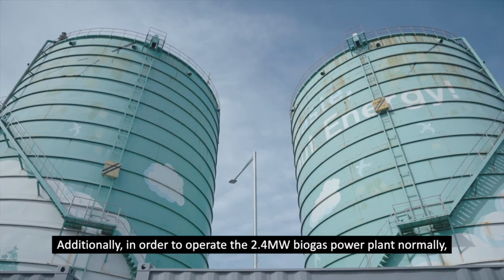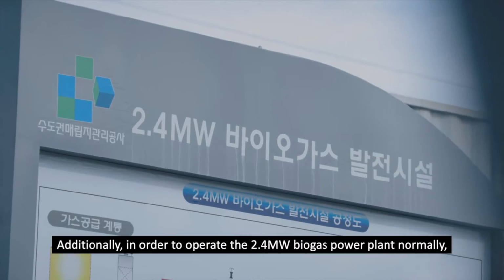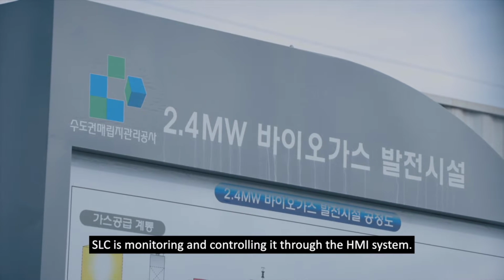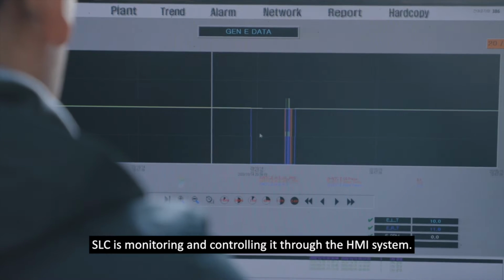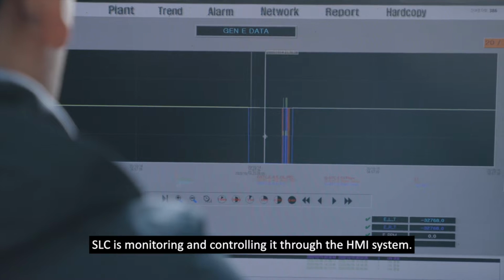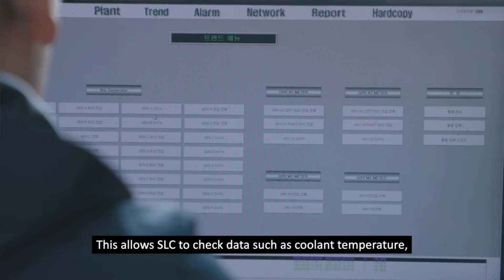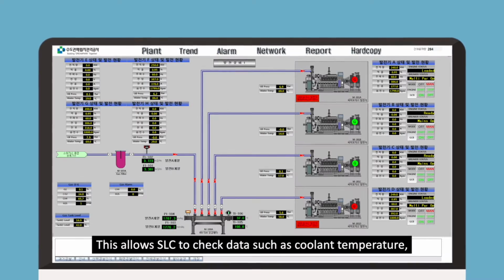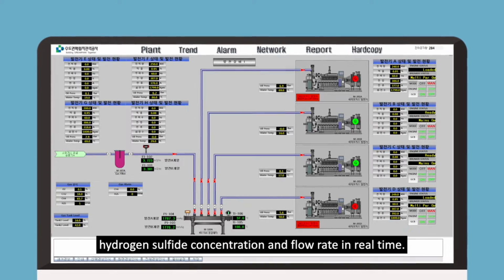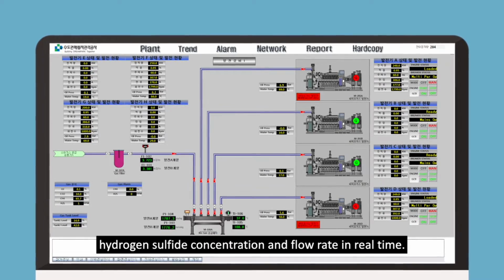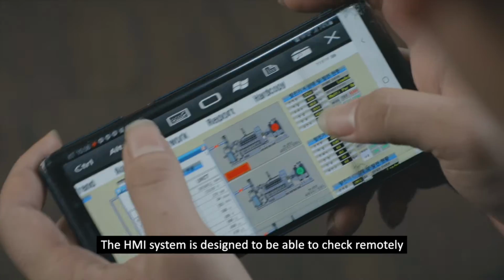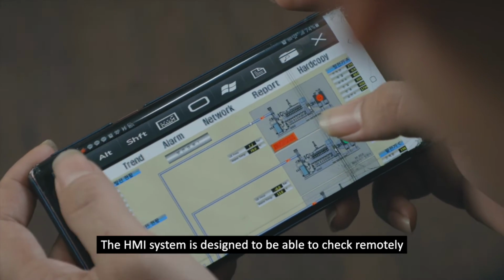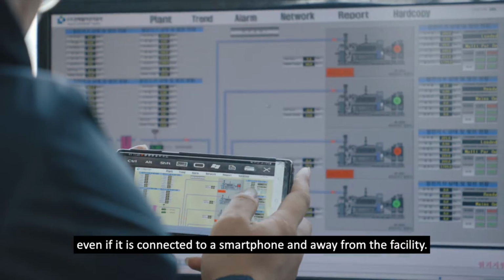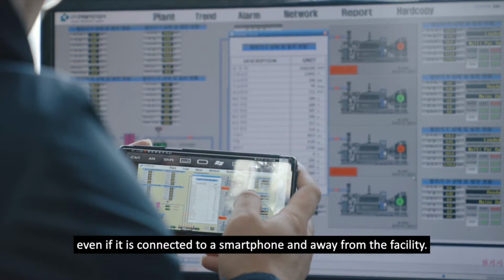Additionally, in order to operate the 2.4 megawatt biogas power plant normally, SLC is monitoring and controlling it through the HMI system. This allows SLC to check data such as coolant temperature, generator status, hydrogen sulfide concentration, and flow rate in real time. The HMI system is designed to be able to check remotely even if it is connected to a smartphone and away from the facility.